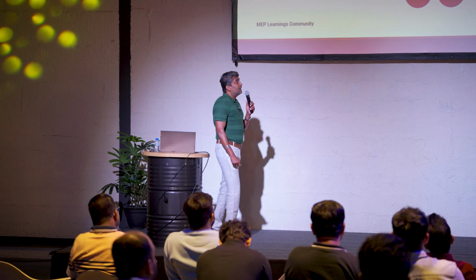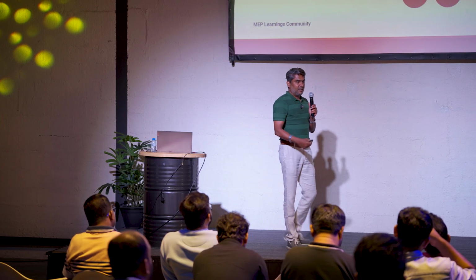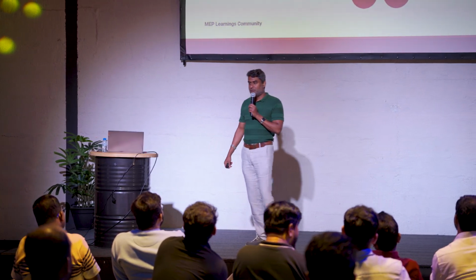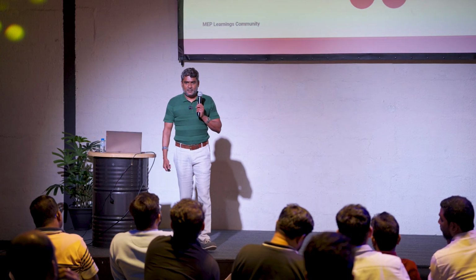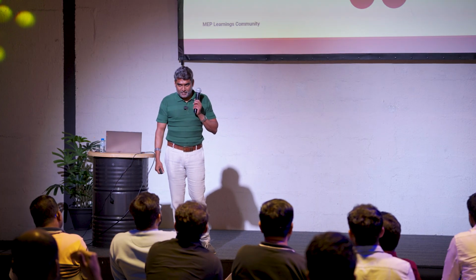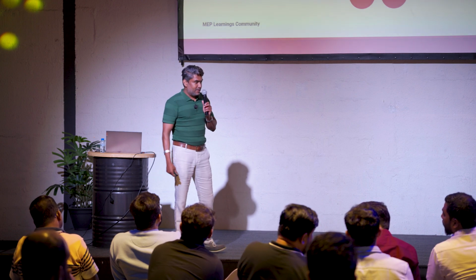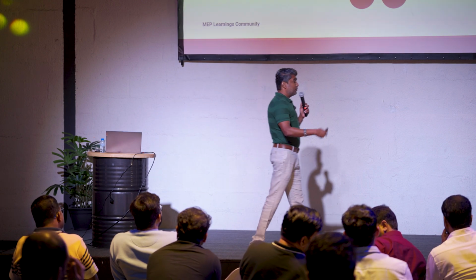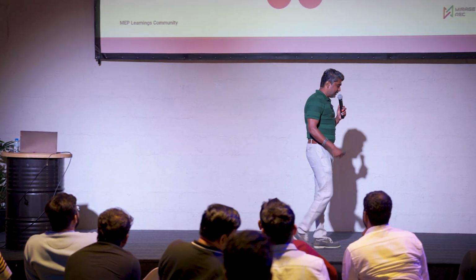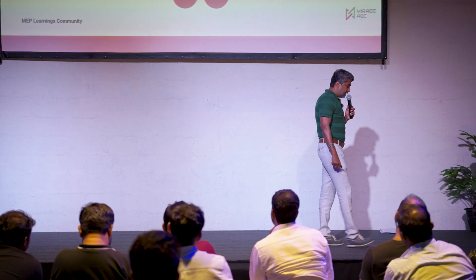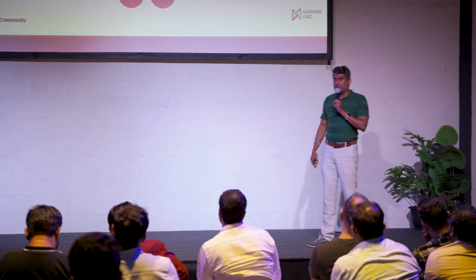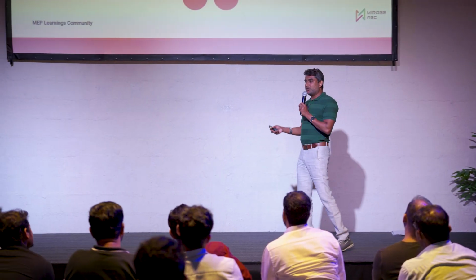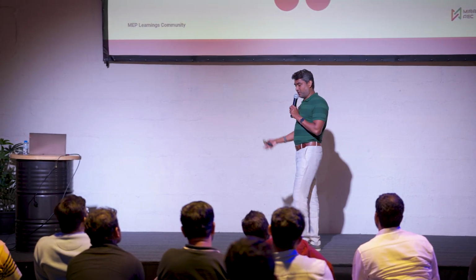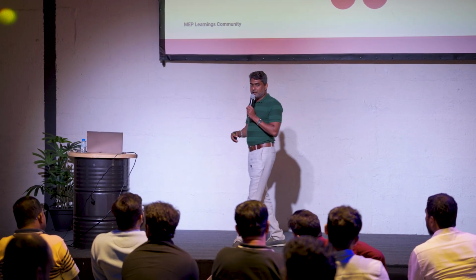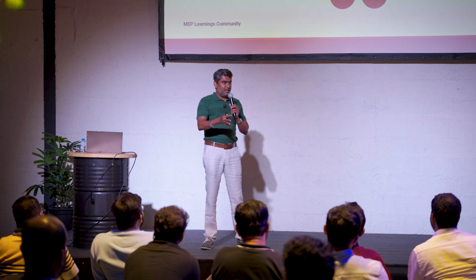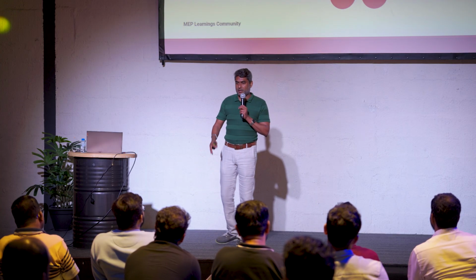The next one is lifts. Why do you think the lifts have to be connected to the fire alarm system? If there are people stuck in the lift while the fire happens... every building you go into will tell you not to use lifts in case of fire, so there will already be people caught in the lift. For that reason, the lift has to go to the designated safe floor, whichever is noted.